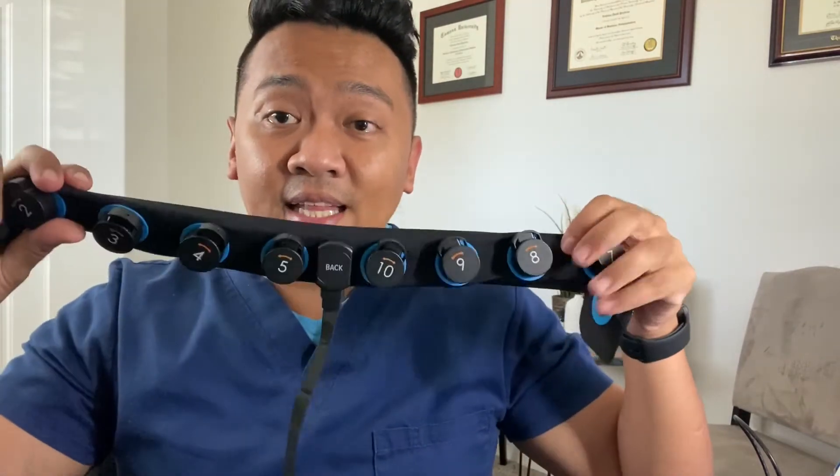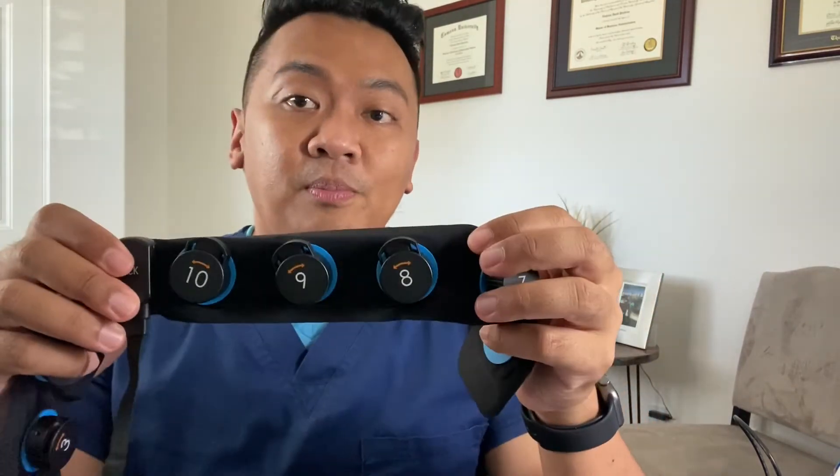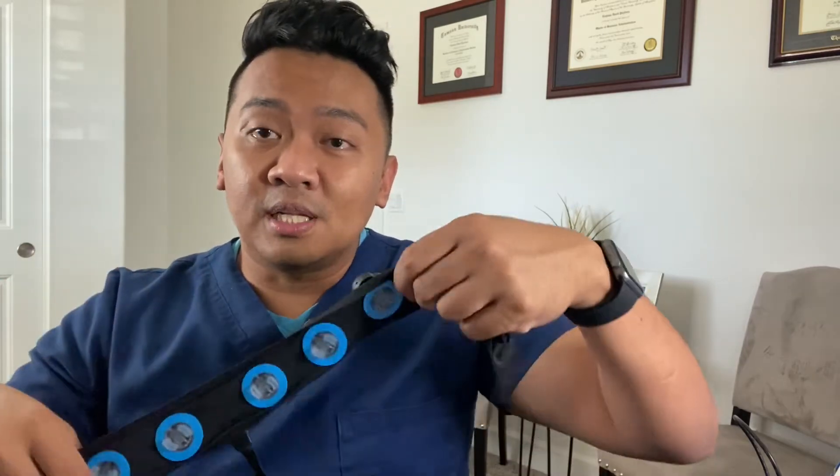The Ceribell headband has 10 electrodes, labeled by number. Pay attention to the label that says 'back.' Place the headband around the patient's head and clip it using the clasp. Make sure the clasp is in the middle of the patient's face. The cord stays at the side and connects to your Ceribell monitor.